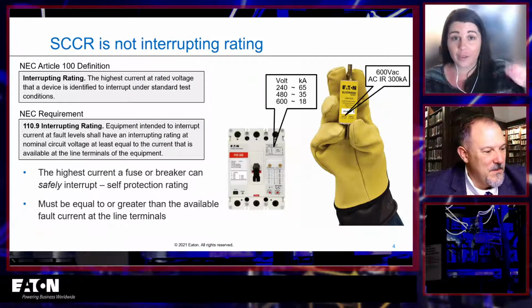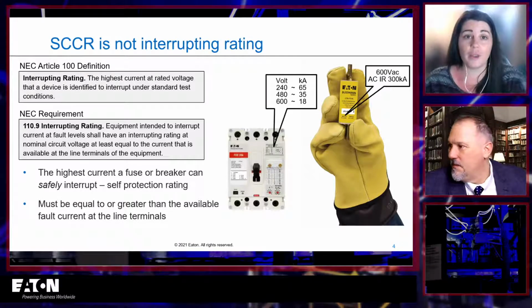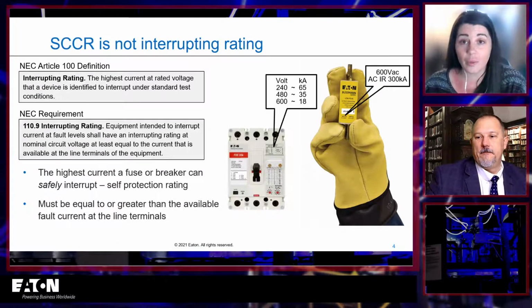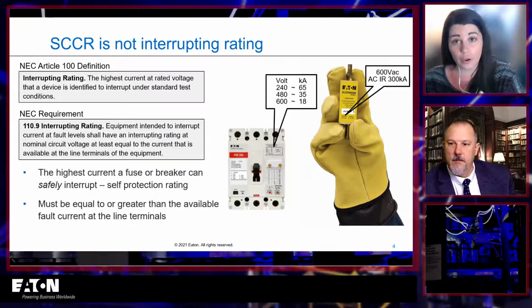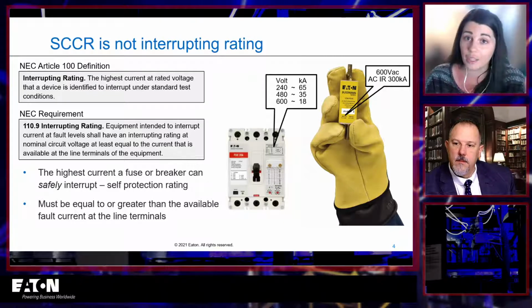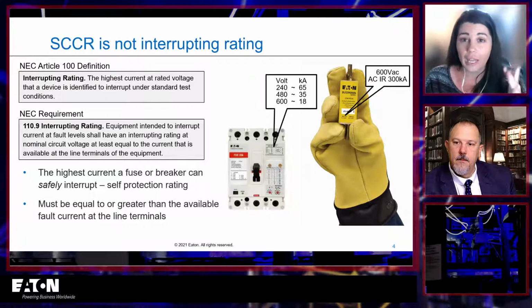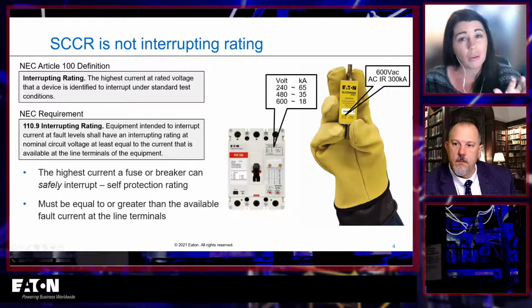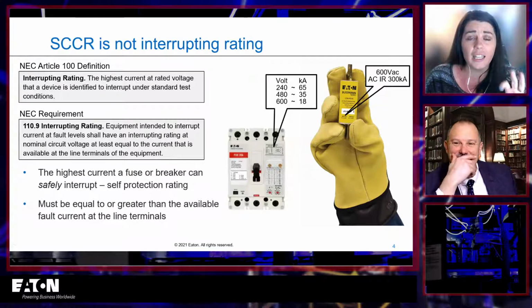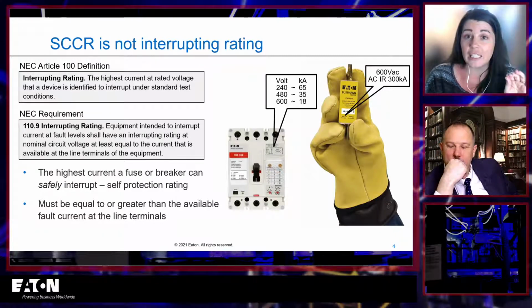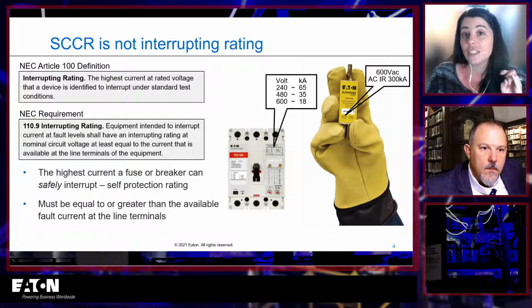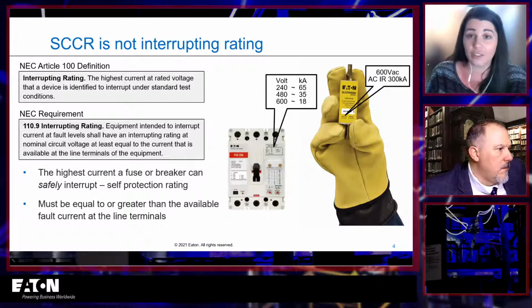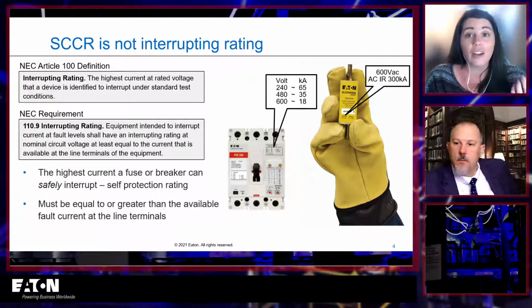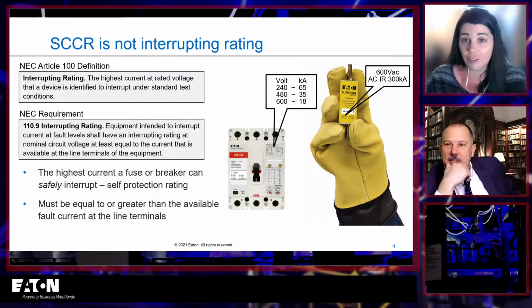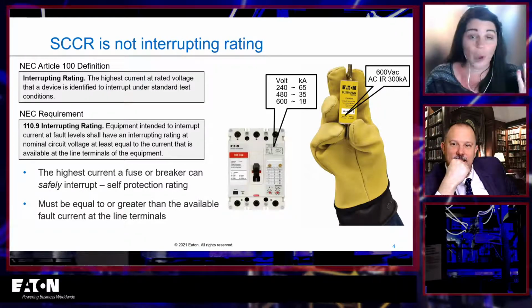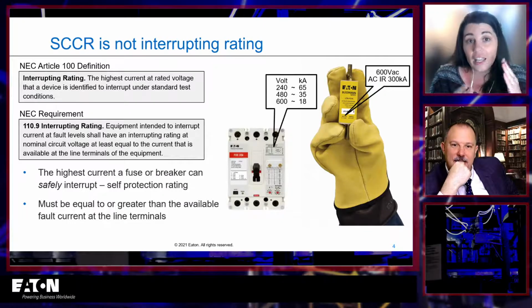All right, so interrupting rating, SCCR, not the same thing as interrupting rating. Interrupting rating is a lot like what it sounds like, but it applies to overcurrent protective devices. When we say overcurrent protective device, we're typically talking about a fuse or a breaker, although sometimes in an industrial control panel, it can be something like a manual motor protector. But the interrupting rating, right? The overcurrent protective device, that's the device that is active during a short. It's what's physically going to open the circuit. The breaker's going to trip, the fuse is going to open. The interrupting rating is the most amount of current that it's rated to safely interrupt. So what is that current that it can interrupt.